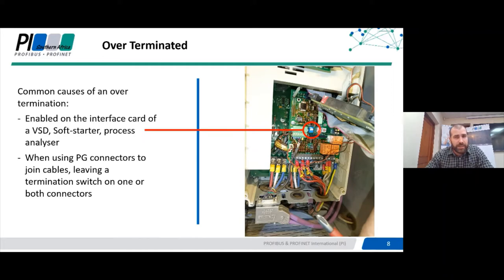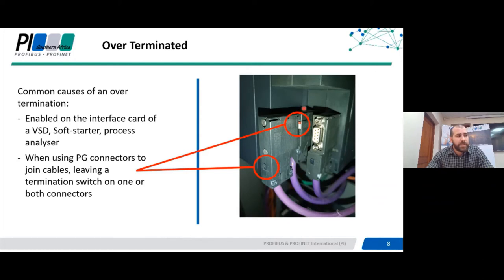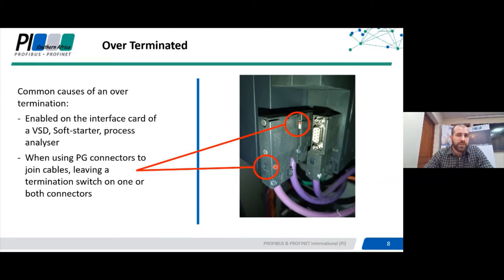Another way over-terminations are typically enabled is through the interconnection of cables using piggyback plugs. This isn't best practice — there's nothing inherently wrong with it and the system will work, but you can accidentally create over-terminations. You have an incoming cable going to a plug connecting the device and the signal goes back out, but in this case we have a double over-termination because there's a terminating resistor enabled on both the bottom and the top plug, which will definitely bring down signal voltages and affect communications across the entire bus. Make sure both terminations are off, or alternatively just wire into one cable rather than connecting cables this way.